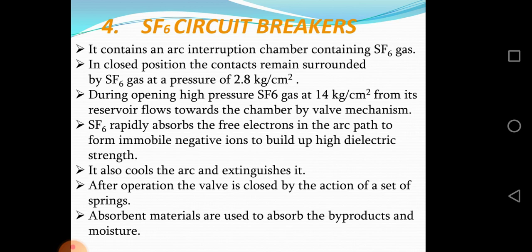Another type is the SF6 circuit breaker. It contains an arc interruption chamber containing SF6 gas. In closed position, the contacts remain surrounded by SF6 gas at a pressure of 2.8 kg per centimeter square. During opening, high pressure SF6 gas at 14 kg per centimeter square from its reservoir flows towards the chamber by valve mechanism.